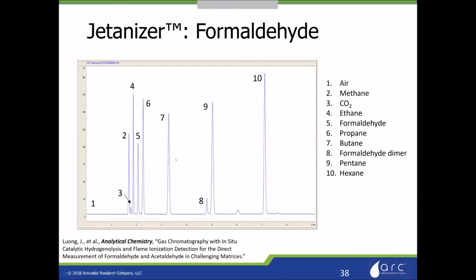So what Jim Luong had to do was actually heat and create his own samples in a glass bomb. And when he did that, he was able to get very good accuracy, within about 5% for formaldehyde, and very nice peak shape, in this case using a DB1 for formaldehyde. So this really opens up a lot of new methods for what is a pretty big hot topic right now, formaldehyde in a number of different consumer products. Moreover, because calibration is so difficult, most of the ways people are calibrating for and analyzing formaldehyde, they're reporting the wrong values. So this could help, because of the uniform response you're getting here, with getting more accurate and reproducible data.